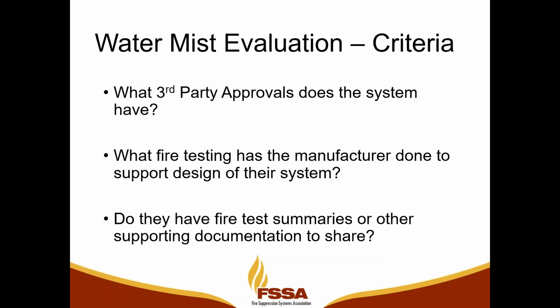So when looking at a water mist type of system, what kind of criteria should you really be looking at? First of all, you need to see what third-party approvals the system has. Does it have FM? Does it have an aspect of UL for OH1? Does it have another agency approval that can be used or recognized in the jurisdiction that you are trying to install or design a system in? Also, if there aren't any third-party approvals, because maybe FM or UL have not developed a particular test protocol for a certain type of area, the next thing you want to look at is what fire testing the manufacturer has done to support the design of their system.